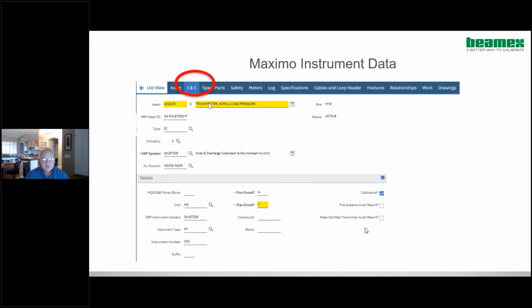The reason it's yellow is we've identified down here that it's a trip circuit. When we know it's a trip circuit, meaning it trips something, we set this to a Y, and it puts this yellow background on it, the same placard that was used by Bechtel which we just continued using. For a fire circuit, we put a Y here, and the background turns red with white letters.